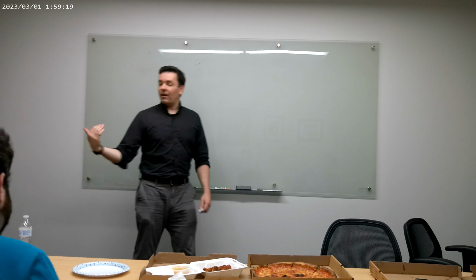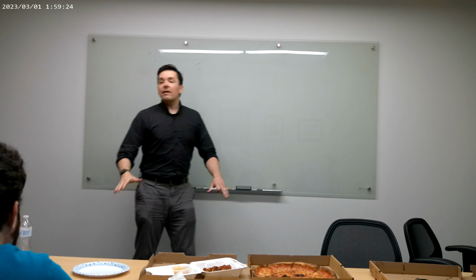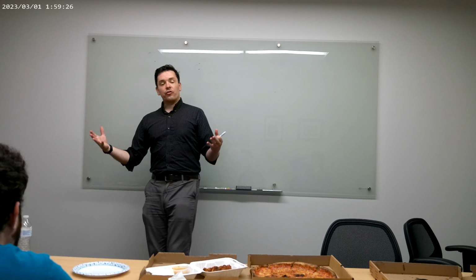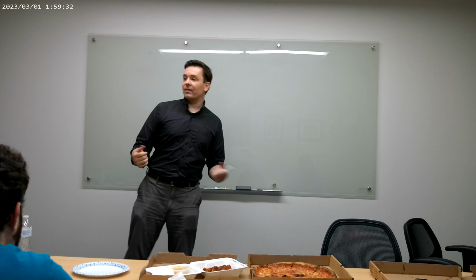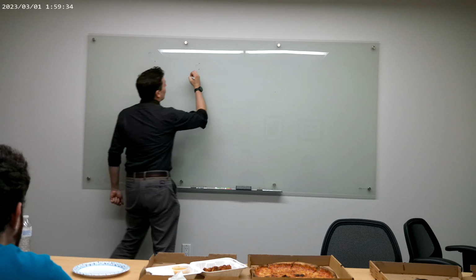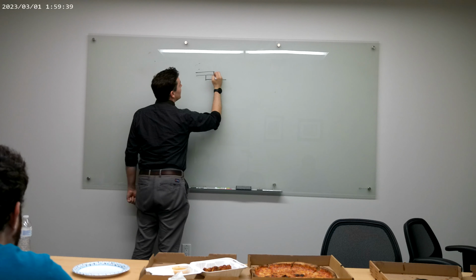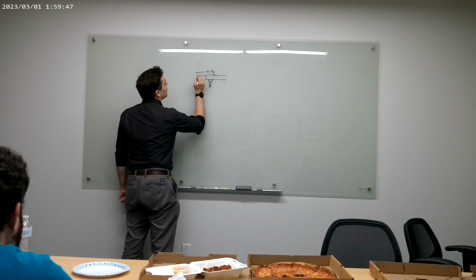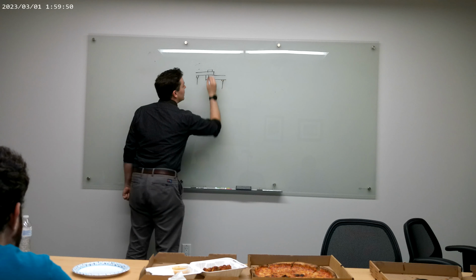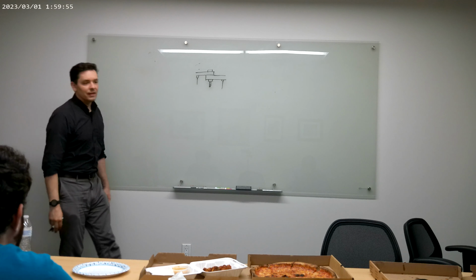So our Ductor is going to apply a known current to a sample. And it's going to determine just how much voltage drops in between the 2 terminals of our Ductor, our contact resistance tester. Because our Ductor is going to be applied to, let's say, a bolted connection where we have 2 pieces of electrical busing bolted together. And we're going to apply our Ductor here and here to measure just how much resistance we have between those 2 contact points that we're dealing with.